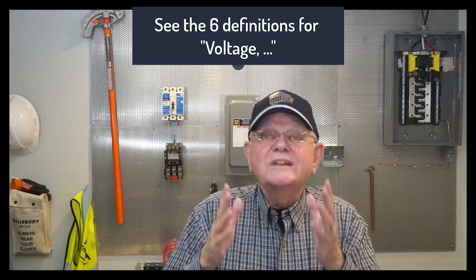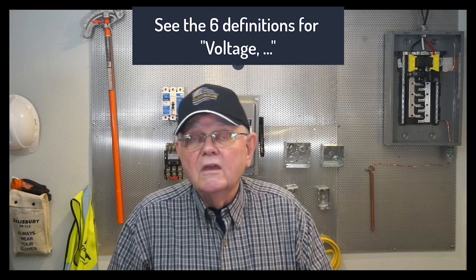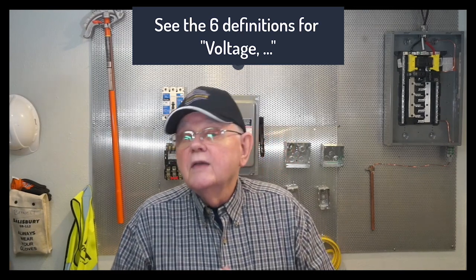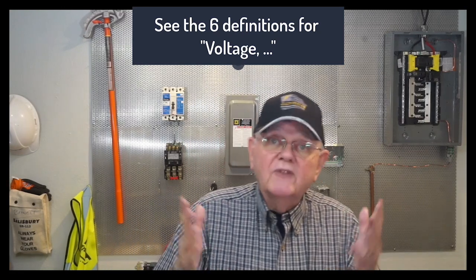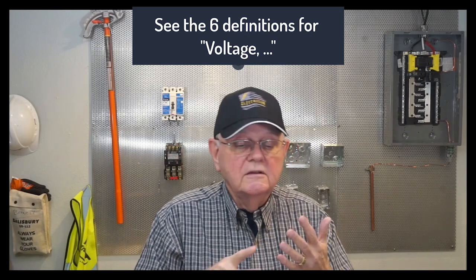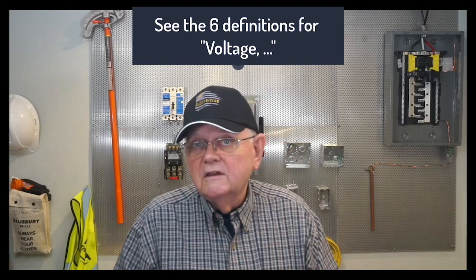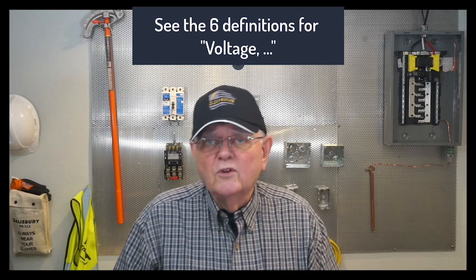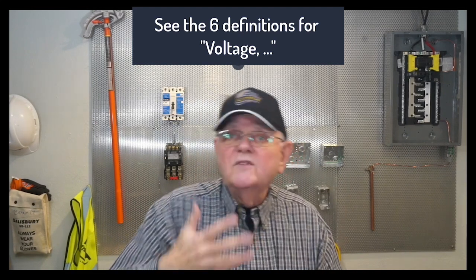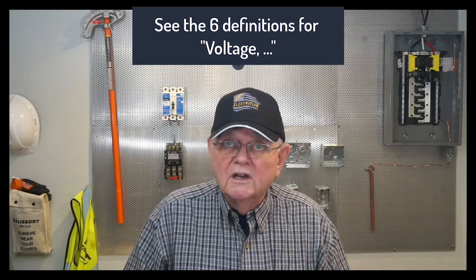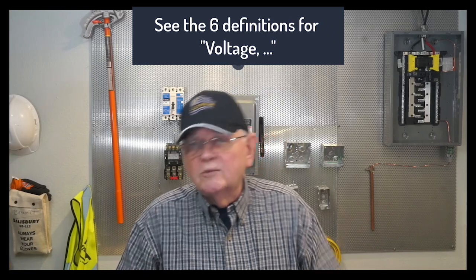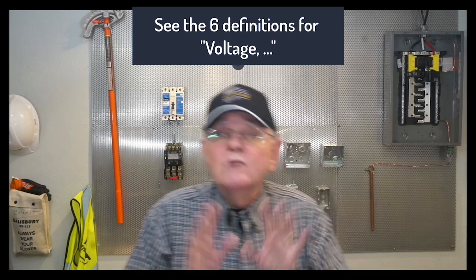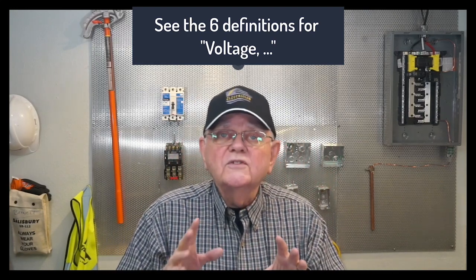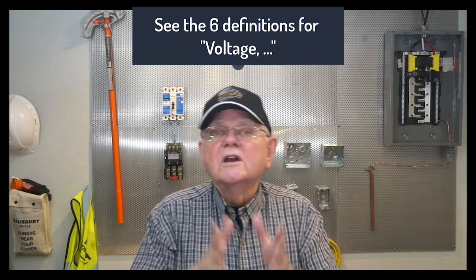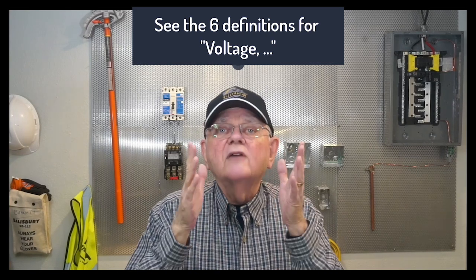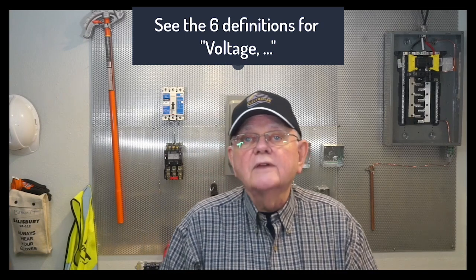If we take a look at the IEEE C37 standards regarding switchgear, we'll find some information on medium voltage switchgear. Medium voltage switchgear is generally rated at either 5 kV, 15 kV, 27 kV maybe, or 38 kV. And usually that's at least as high as I've seen on medium voltage switchgear, and we call that medium voltage. So in a 5 kV switchgear, we'd put 4160 nominal system voltage, and 4160 breakers, we'd call them, though they're rated for 5 kV and all of that. So anyway, a little bit of confusion there with the high voltage. But once again, if the code somewhere under equipment or wherever talks about high voltage equipment, whatever it is, it's talking about something being rated more than 1,000 volts. Okay? Potential difference of more than 1,000.